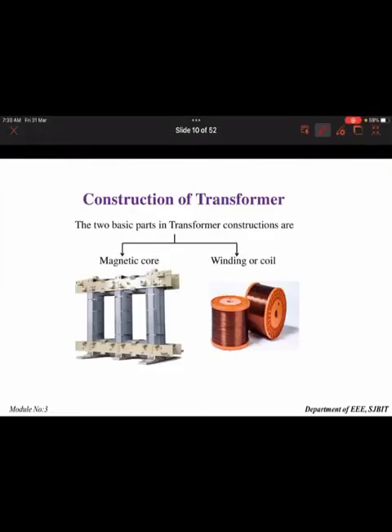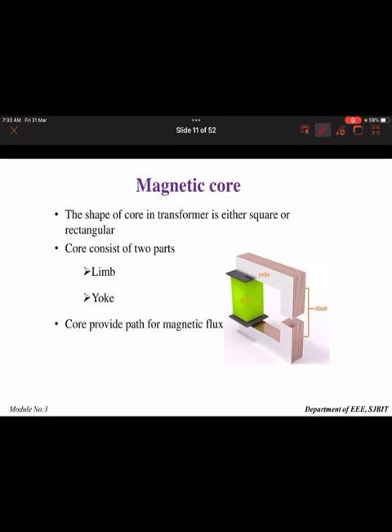Regarding the construction of a transformer, the two major parts are the magnetic core and the winding coil. The magnetic core is either square or rectangular in shape and consists of two parts: the limb and the yoke. The horizontal parts are called the yoke and the vertical parts are called the limb. The core is used to provide the path for the magnetic flux, and it is made up of thin laminated sheets insulated from each other.